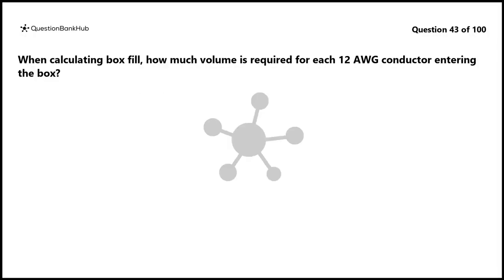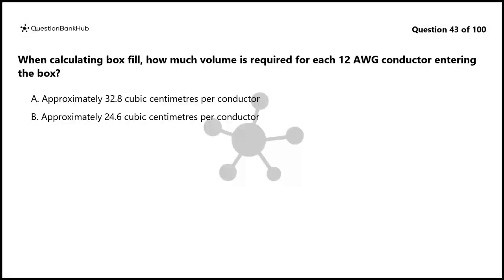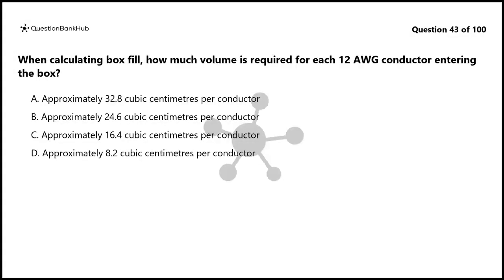Question 43. When calculating box fill, how much volume is required for each 12 AWG conductor entering the box? A. Approximately 32.8 cubic centimeters per conductor. B. Approximately 24.6 cubic centimeters per conductor. C. Approximately 16.4 cubic centimeters per conductor. D. Approximately 8.2 cubic centimeters per conductor.